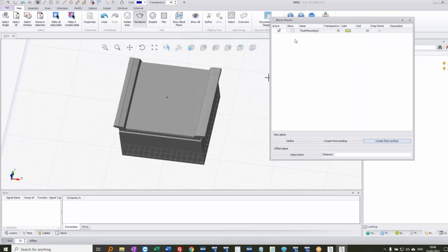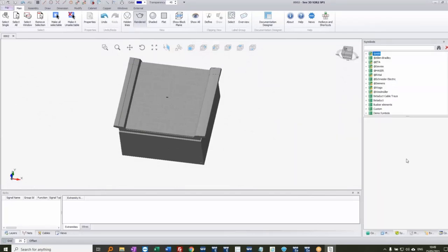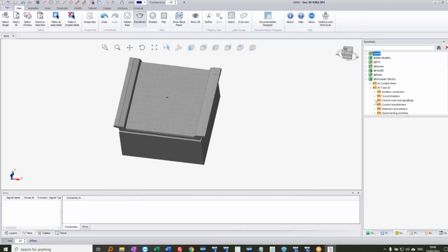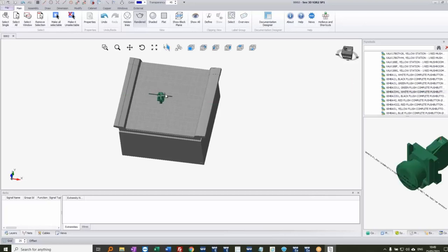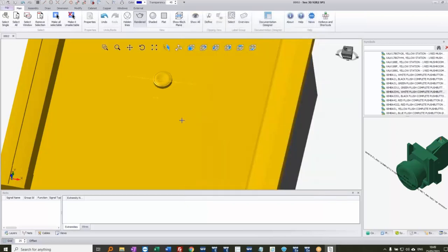With the working plane set, I can go into symbols and choose a Schneider control unit — a push button — and as I move it over this area I can click to place it. Right-clicking and choosing 'Show drill template' confirms it has the correct information — showing the outline of the component and the required drill hole. In a very short time I've taken an unintelligent STEP file and created an intelligent enclosure ready to have components added to it.